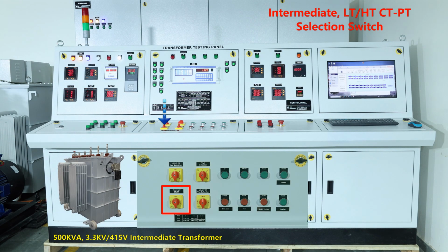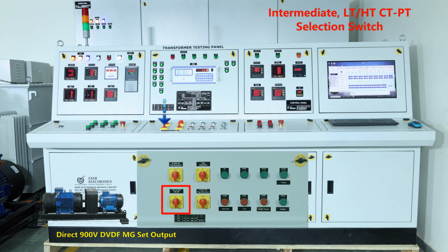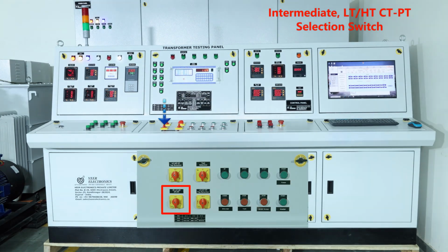Second is the 500 kVA, 3.3 kV by 415 volts intermediate transformer, to perform short circuit and temperature rise tests of the transformer. Third intermediate selection is 900 volts direct output for DVDF test of distribution transformer. HT and LT, CT and PT are also selected by this switch.